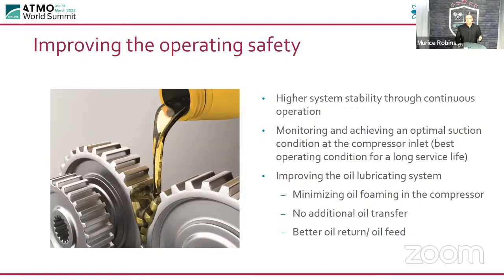So with the improvements of the operational safety, higher stability, monitoring and achieving optimal suction conditions at the compressor inlet, so the best operating conditions for long service life. So this actually extends the performance of the actual pack a lot longer than what it would normally, where compressors may be running outside of the envelope. And the lubrication system is also not compromised at all.